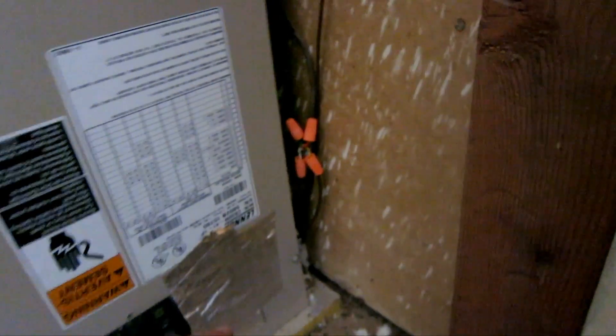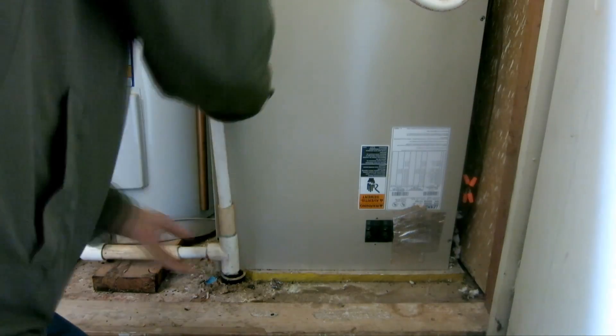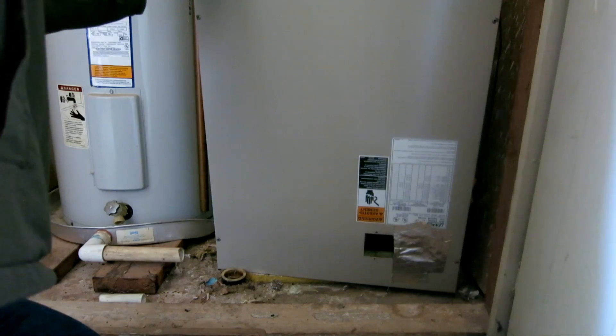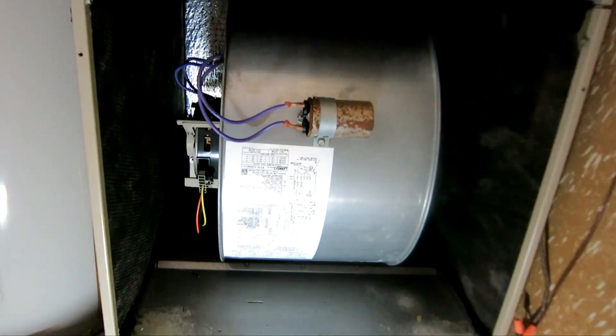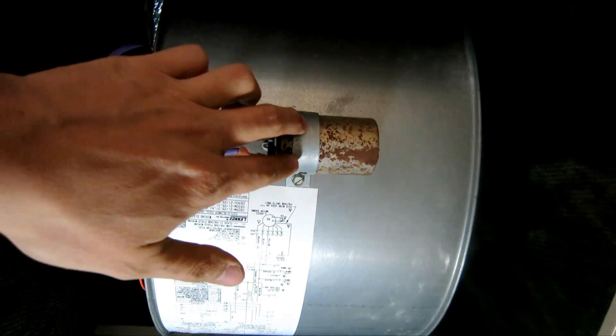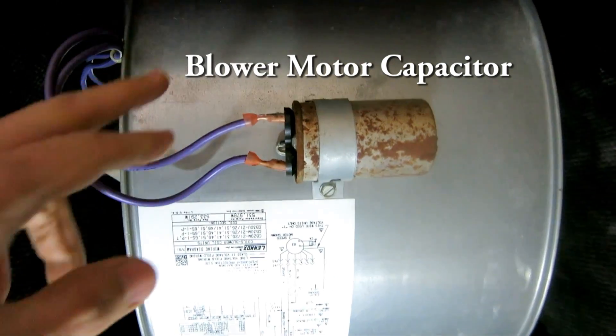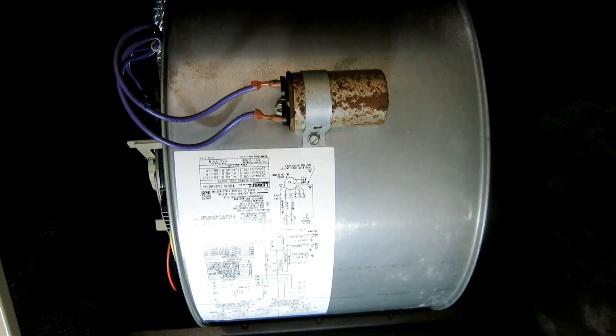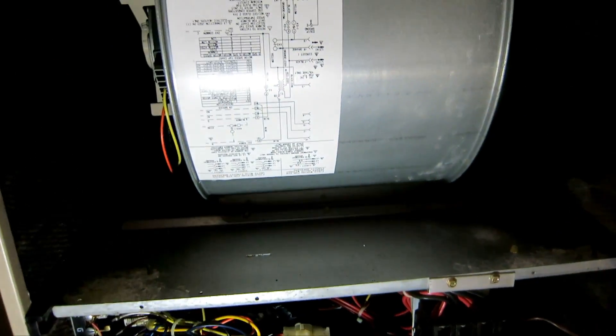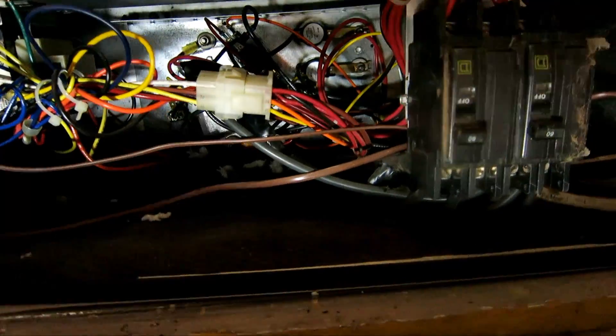After the panel is off, the top part is a fan. That's the capacitor for the fan. It's rusted out, looks like there's a little bit of corrosion on the side. We're going to test that capacitor. If it's bad, that means the fan isn't running efficiently and could cause it to draw a little bit more current than normal.